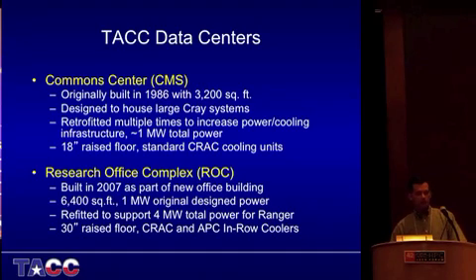In 2007, we were lucky enough to be working with another group and got a new building, which is very unusual on university campuses. At the time, we were working with the facilities folks and kept trying to explain to them our requirements: we wanted 12,000 square feet and 5 megawatts of power. They said no, you're never going to need that much space or power, and that they'd give us 6,400 square feet and 1 megawatt of power. Sure enough, we were then awarded the Ranger system shortly thereafter, which required 2.4 megawatts of power, so the machine room was refitted shortly after being commissioned to now support 4 megawatts of total power, but we're still only limited to about 6,400 square feet total in the room.